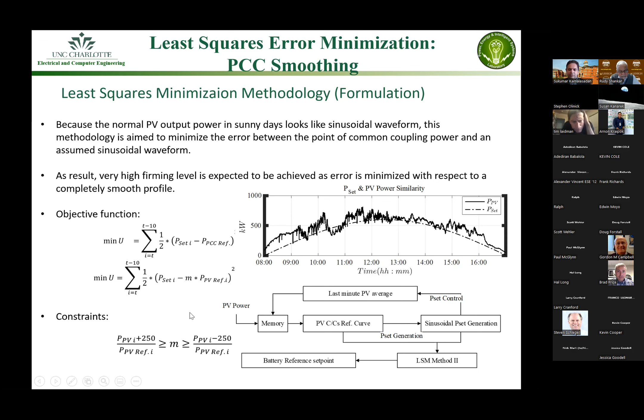Here are some output reference graphs. You can see from the older historical values, you can create a minimum and maximum change for those historical values, and then develop a PCC reference curve. With the help of this PCC reference curve, you can provide a set point to your battery energy storage.